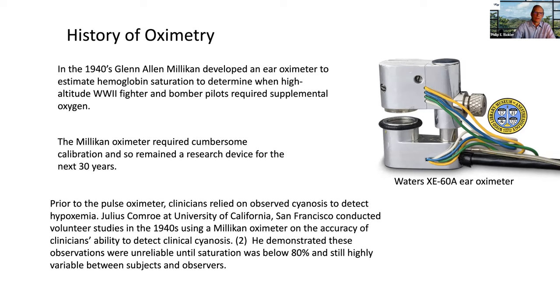So Glenn Millikan developed an ear oximeter, and there's a picture of it on the right there. In order to calibrate it, it had to squeeze the blood out of the ear. So that little clamp device there is used to produce basically a zero signal with no blood in the ear. Well, this is a very awkward type of device, and you can see it hardly looks like something you'd want to wear on your ear for very long.